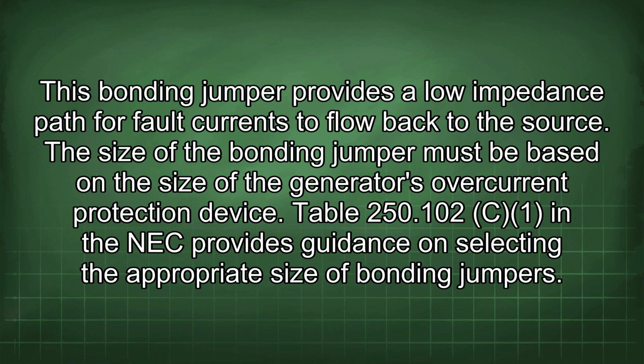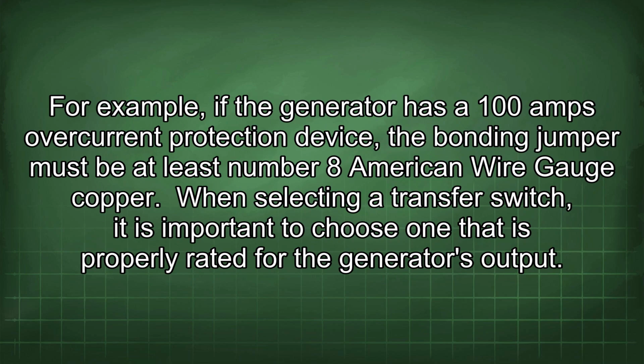Table 250.102 in the NEC provides guidance on selecting the appropriate size of bonding jumpers. For example, if the generator has a 100 amps overcurrent protection device, the bonding jumper must be at least number 8 American wire gauge copper.